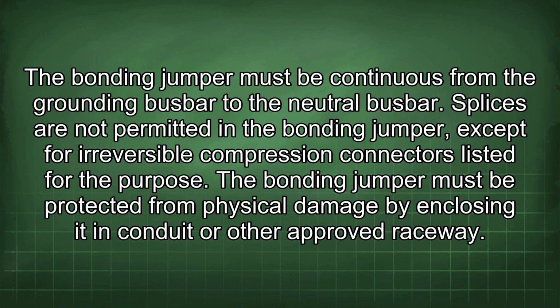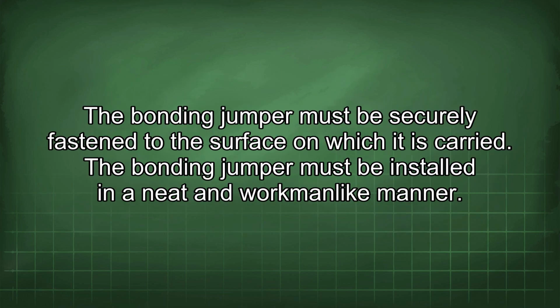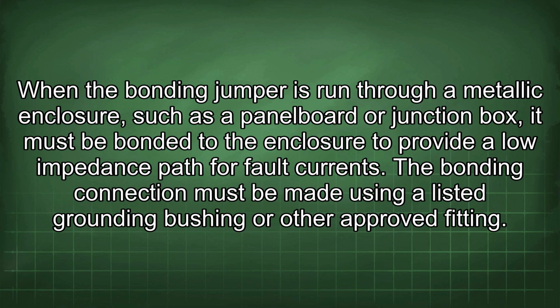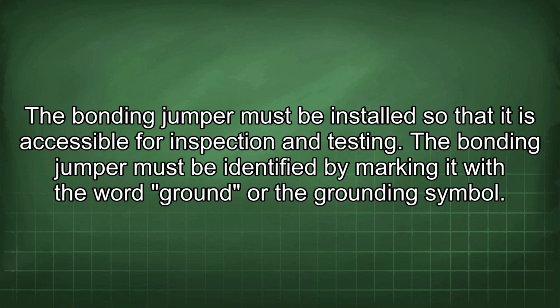Splices are not permitted in the bonding jumper except for irreversible compression connectors listed for the purpose. The bonding jumper must be protected from physical damage by enclosing it in conduit or other approved raceway. The bonding jumper must be securely fastened to the surface on which it is carried. The bonding jumper must be installed in a neat and workmanlike manner. When the bonding jumper is run through a metallic enclosure, such as a panel board or junction box, it must be bonded to the enclosure to provide a low impedance path for fault currents. The bonding connection must be made using a listed grounding bushing or other approved fitting. The bonding jumper must be installed so that it is accessible for inspection and testing. The bonding jumper must be identified by marking it with the word ground or the grounding symbol.